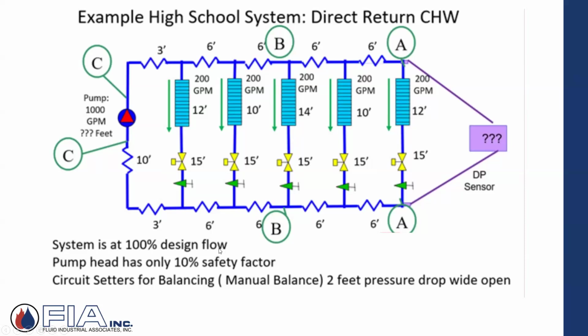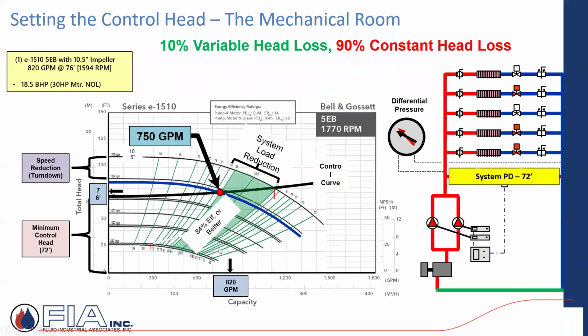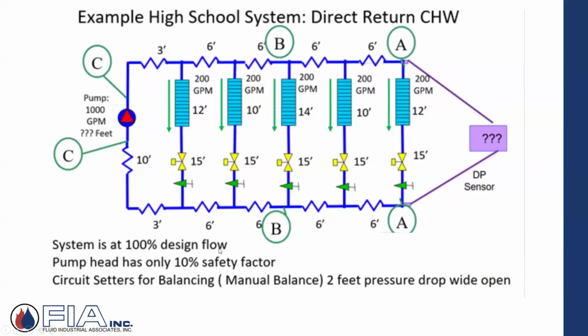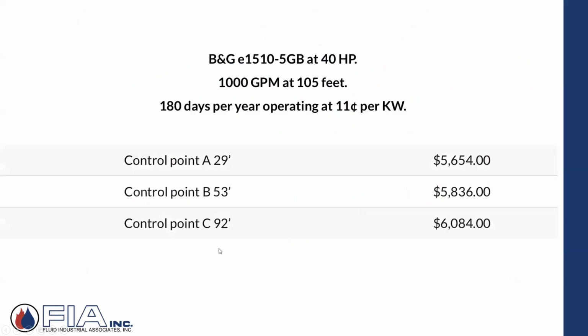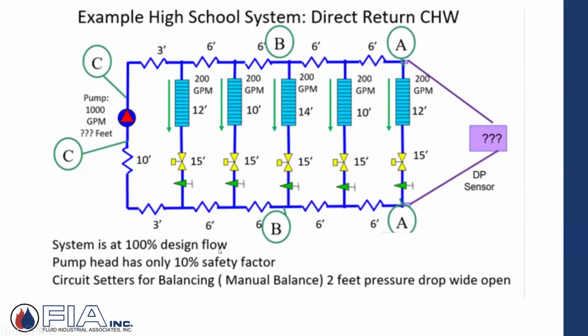This is just showing what happens, and it's a follow-up to that picture here. If I'm in the mechanical room, here's my distribution pump, and I have A, B, and C. Where do I put that DP sensor? All the way to the end, maybe halfway, or again, back in the mechanical room. And what that impact is on savings, on speed reduction. And then just plugging in some numbers and what the change would be. But there is a difference between controlling it at A versus B versus C.